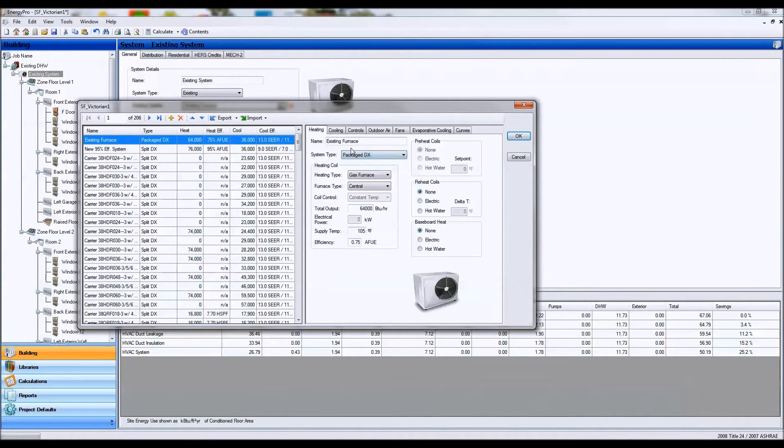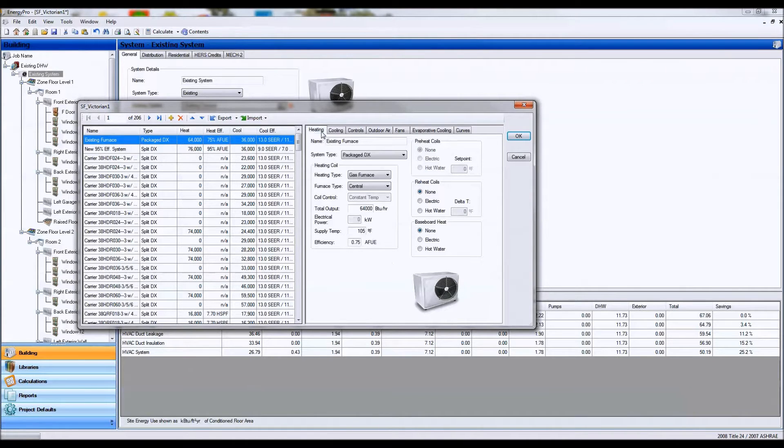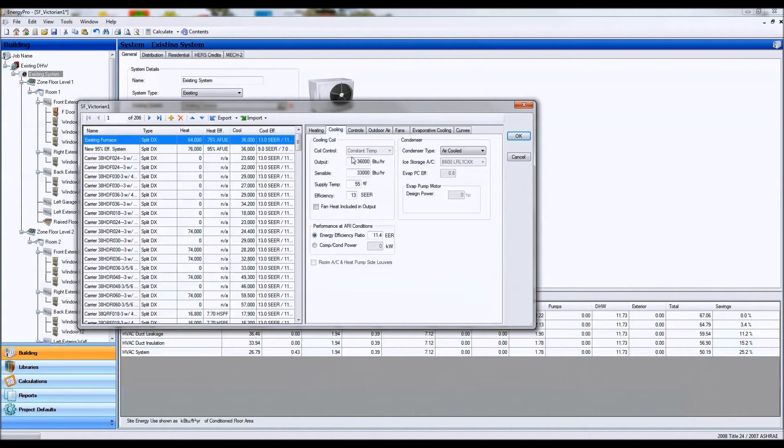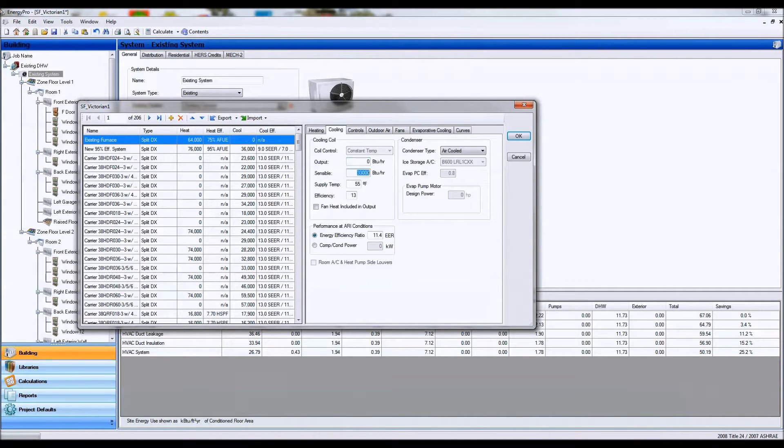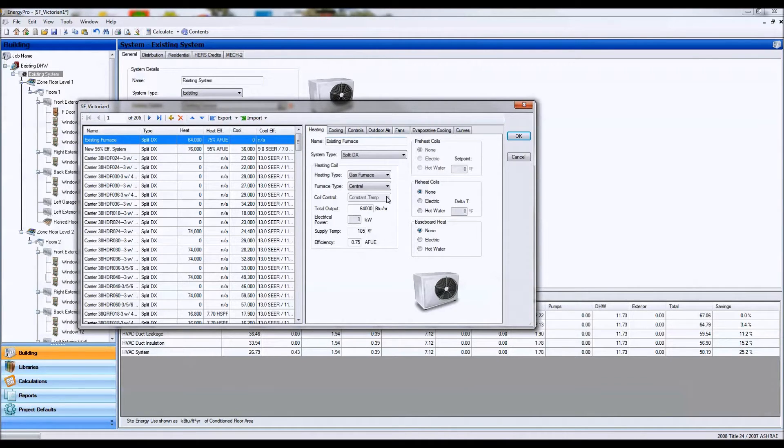If I have a package unit, these typically have cooling systems. Sometimes split systems won't have cooling systems. So if that's the case, you're going to go ahead and zero out the outputs in the sensible, and Energy Pro will see the efficiency is zero and only look at the heating efficiencies.